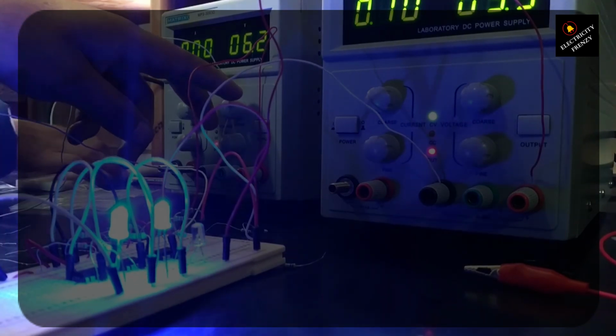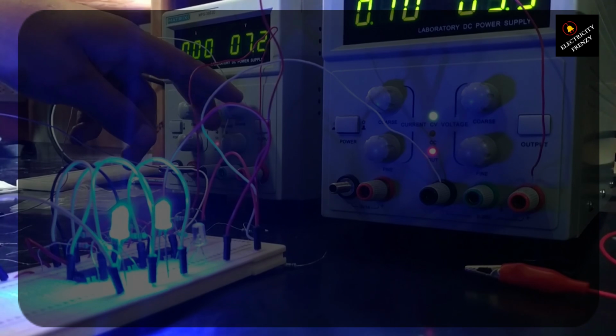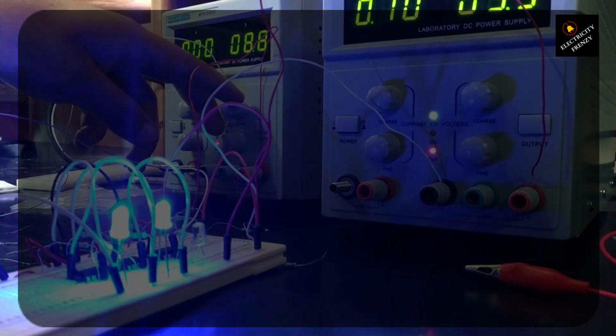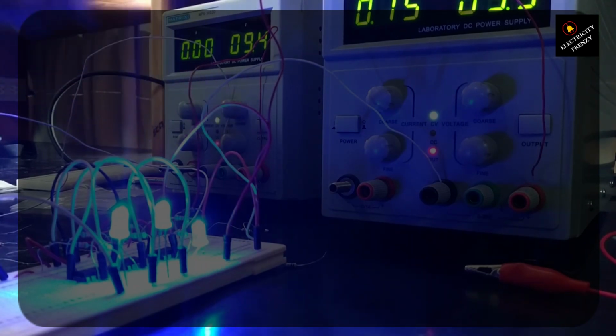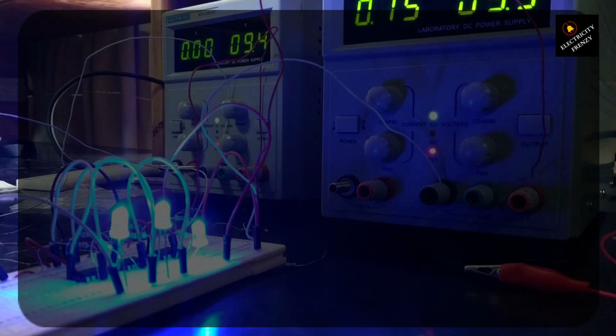1. Short circuit. A short circuit happens when a hot wire touches either a neutral wire or a ground wire, causing a sudden surge of current and an instant tripping of the breaker. This is different from an overload, as in a short circuit, if you try to turn on the breaker, it will trip immediately and may produce a spark inside it.